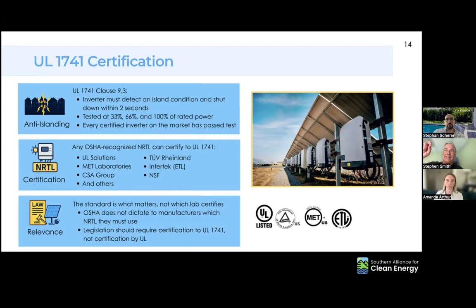What we need to clarify is that the only danger is if the grid goes down and the system continues generating power, which could then be fed back onto a disabled utility distribution network. We want to emphasize very clearly: if you have a certified UL 1741 inverter, this will not happen—it does not happen. So this concern about people being injured by solar largely doesn't exist, because these inverters are so good.